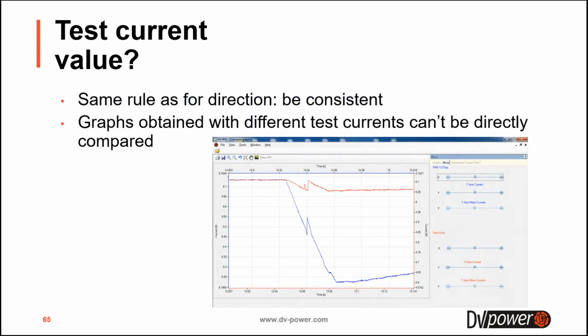So again, the same rule as for the direction. It's important to be consistent. If you recorded previously with 10 amps, then use 10 amps again. You can see here down below again the comparison. The same transformer, the same tap changer, the same transition. Red is the lower current, blue is the higher current. You can see the timing is the same, but the graph obtained with the higher current, the blue one, is easier to analyze.